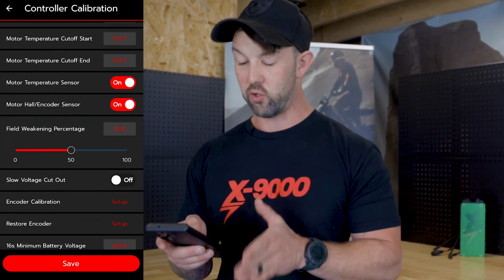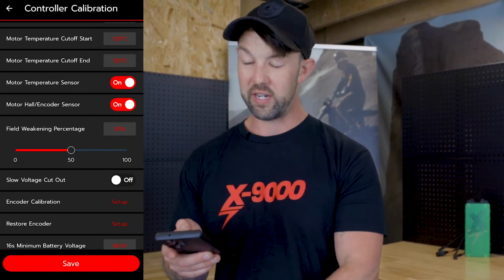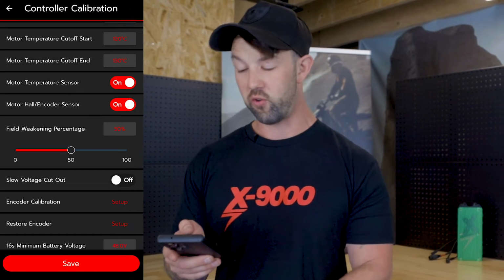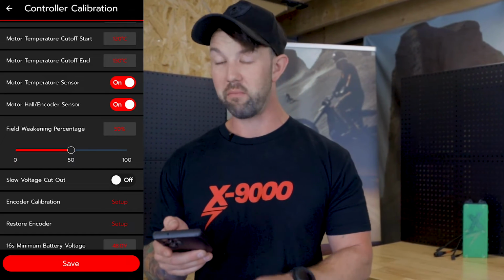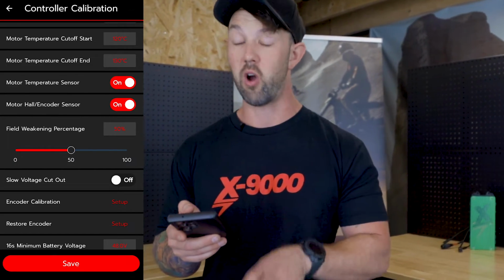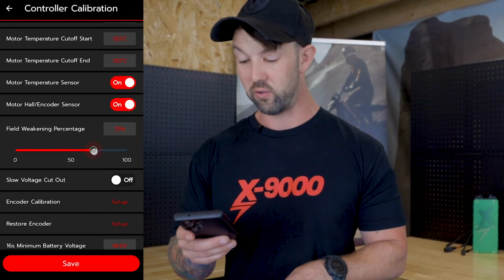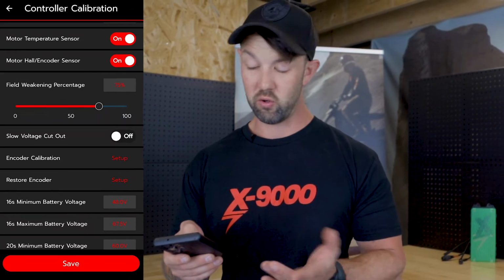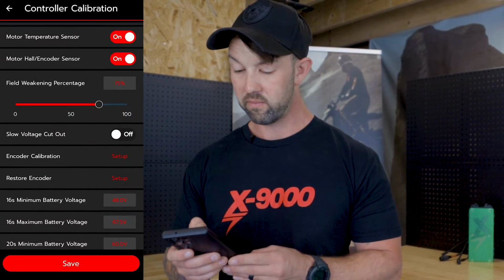Another one to look at here is your field weakening. Field weakening will increase your top speed. On this motor, 70 to 80% is a good place to be. I would not recommend going above 80%, because the heat that is induced into the motor is too great. So I'm going to change this to 75%. Click save. If you ever need to calibrate your encoder again, you can do that here.